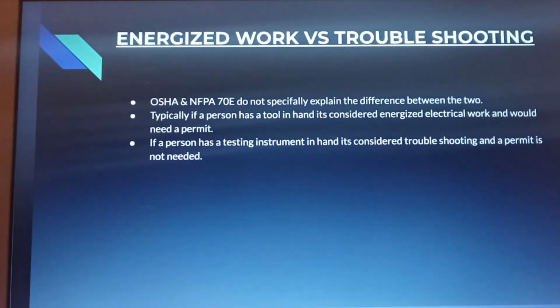All right, so energized work versus troubleshooting. OSHA and NFPA 70E do not specifically explain the difference between the two, but typically, if a person has a tool in hand, it is considered energized electrical work and would need a permit. But if the person has a testing instrument in hand, it's considered troubleshooting and a permit is not needed.